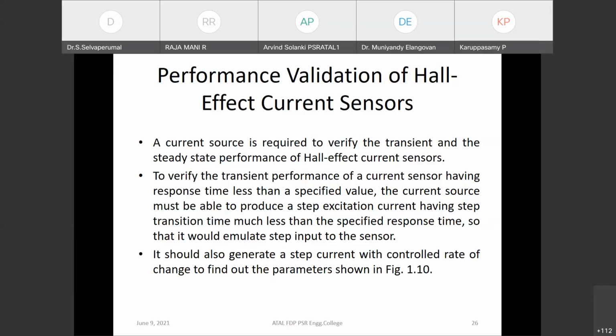The linearity and the accuracy of the sensor output must be verified for DC excitation at rated value. To verify all these steady state characteristics, the current source should be able to produce DC and sinusoidal reference current at the rated value with variable frequency up to a sufficiently large value. While generating continuous sinusoidal current, it should draw minimal active power from the main supply to reduce electricity consumption during the heat run test.